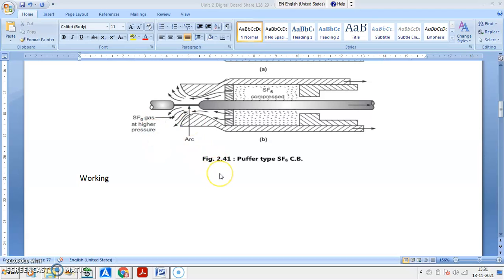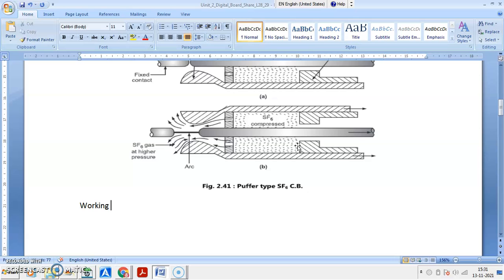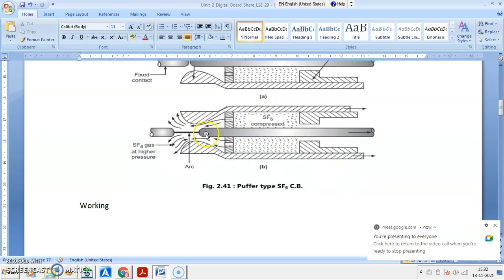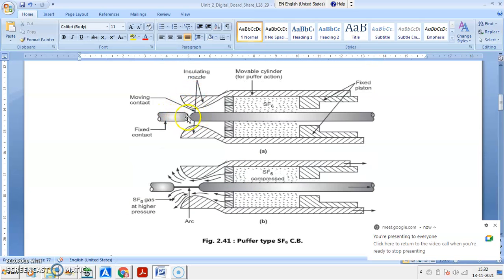Working action of puffer type SF6 gas circuit breaker is shown in the figure. Now in this, you can see the puffer action of the cylinder. Under normal operating condition, contacts are closed. Here, contacts are closed.